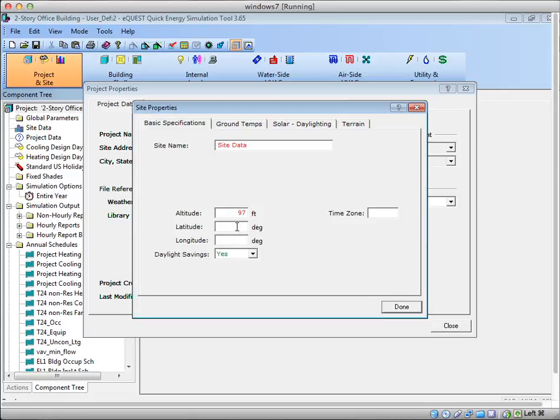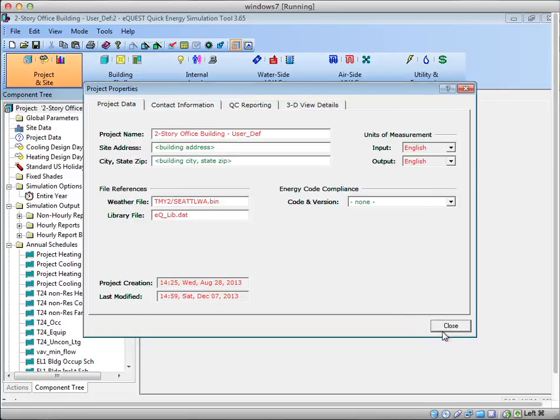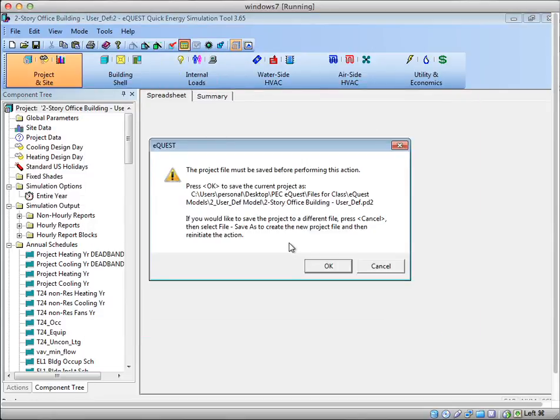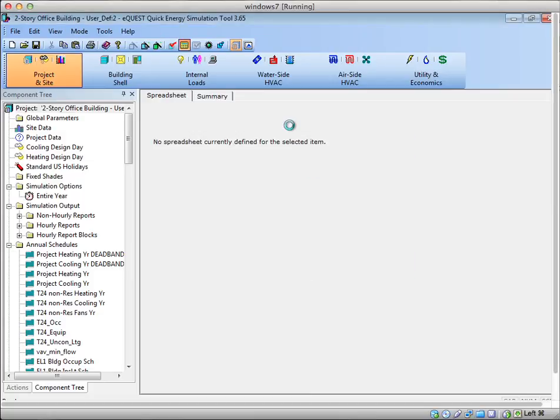You don't actually need them to run the model. I'm going to go ahead and hit Run—the yellow button. What will happen if the latitude and longitude are not defined is eQuest will look at the weather file, which has that information, and use that instead.